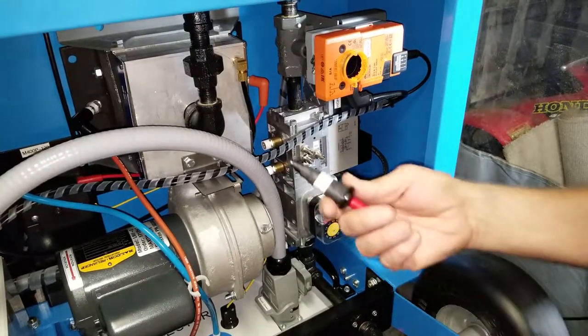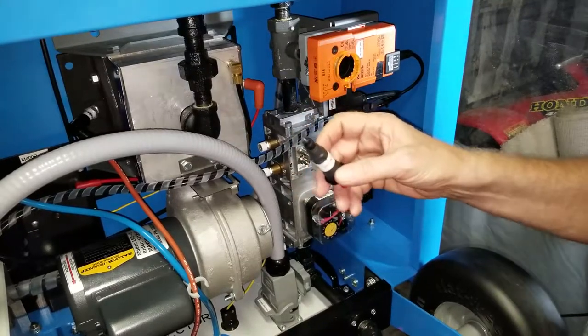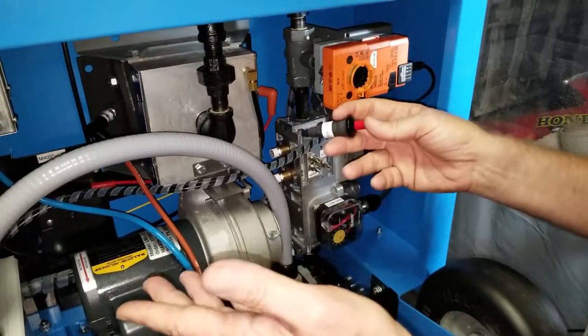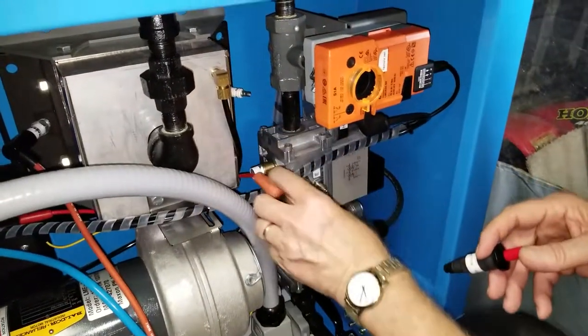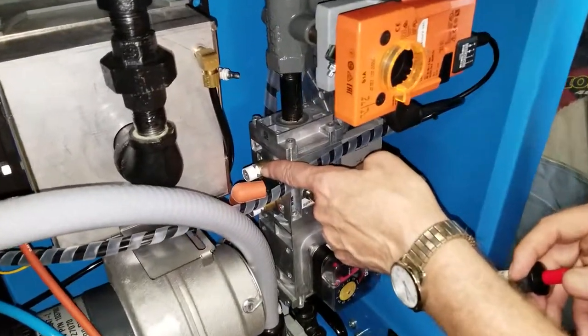In this video, we're going to talk about how to manually ignite the heat injector with a manual piezo — a lighter. Basically, if the high voltage transformer is not working, you're going to remove the boot. After you remove the boot, you're going to watch for these visual indicators.